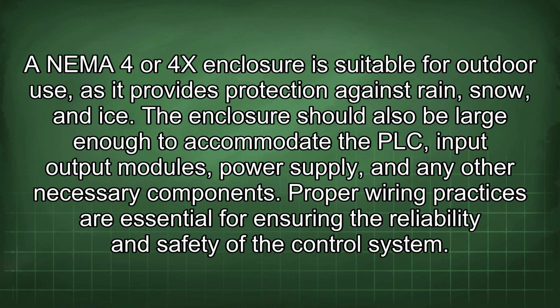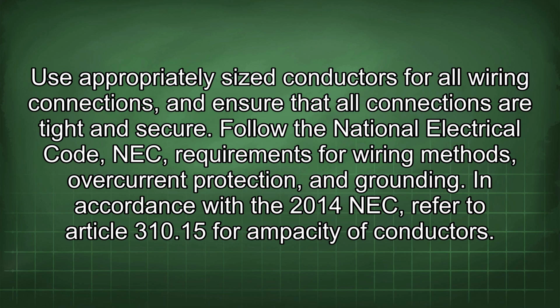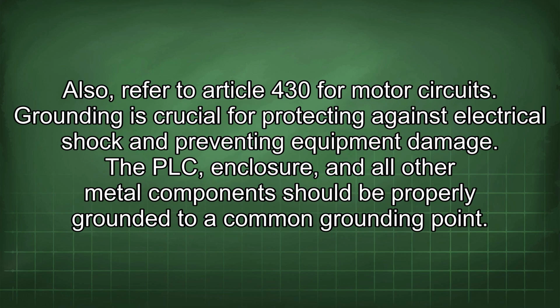Proper wiring practices are essential for ensuring the reliability and safety of the control system. Use appropriately sized conductors for all wiring connections and ensure that all connections are tight and secure. Follow the National Electrical Code (NEC) requirements for wiring methods, overcurrent protection, and grounding. In accordance with the 2014 NEC, refer to Article 310.15 for ampacity of conductors. Also, refer to Article 430 for motor circuits.